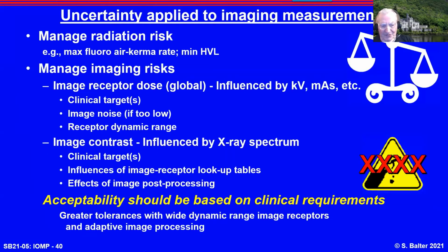We're doing this to manage risk, radiation risk. We're doing this to manage imaging risk. Imaging, if the radiation is too low, there are noise issues. These depend on the targets. Receptors have dynamic range. Image contrast will be affected by the targets. In addition to the X-ray spectra, there are influences on the receptor lookup tables, post-processing. You need to look at the clinical requirements and decide what tolerances can be accepted. This, again, is a professional judgment.